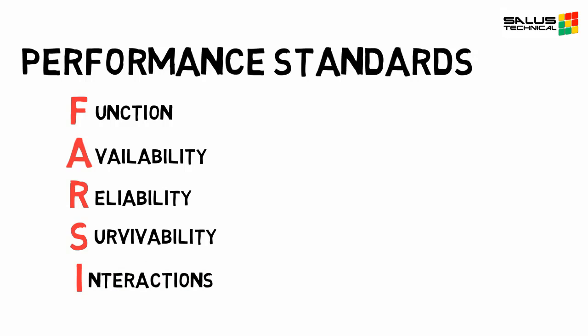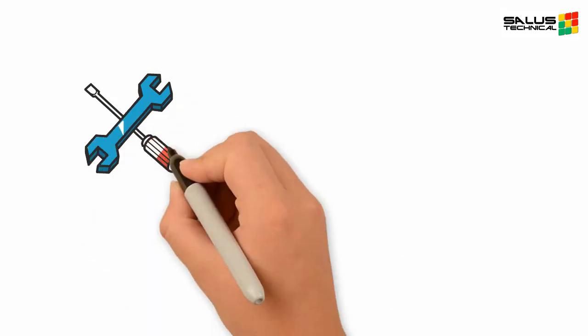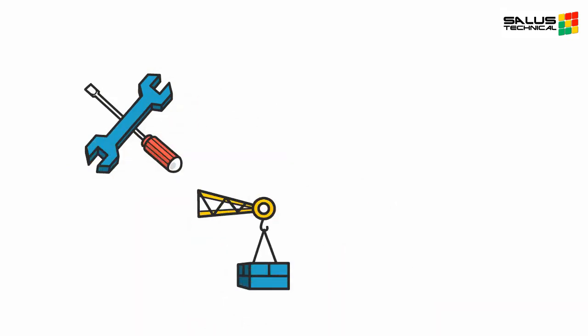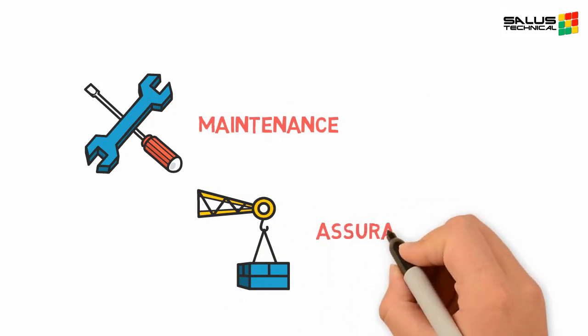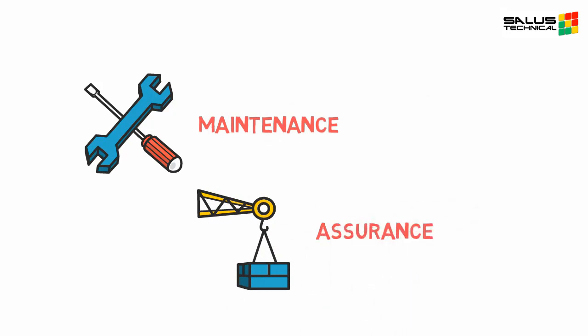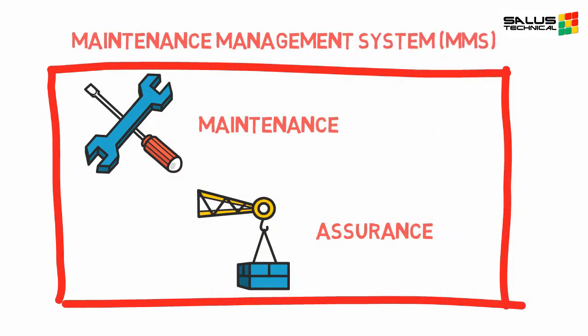We must ensure that SECIs remain fit for purpose throughout the life of an installation, and function when required to do so. We do this by conducting routine maintenance, as well as assurance, where we test specific parts of the SECI's functionality. Results of these are recorded within the maintenance management system. Every maintenance and assurance activity should have a clearly defined failure criteria, which we usually define within the performance standards.